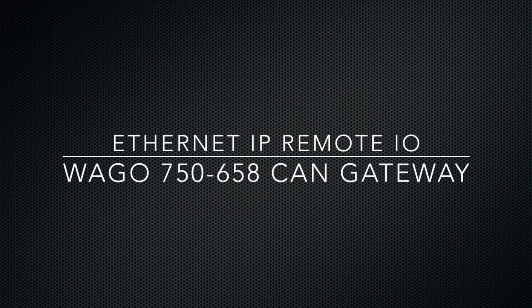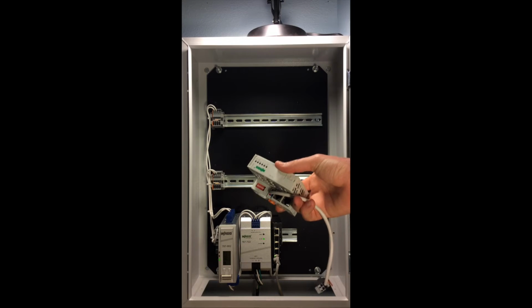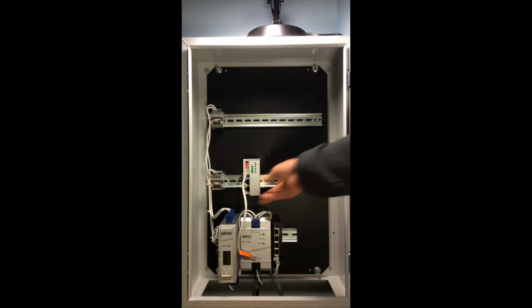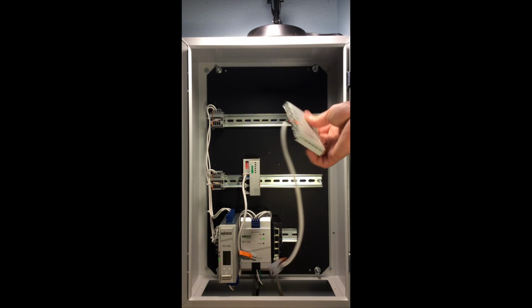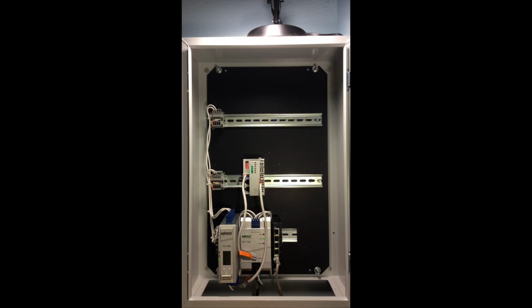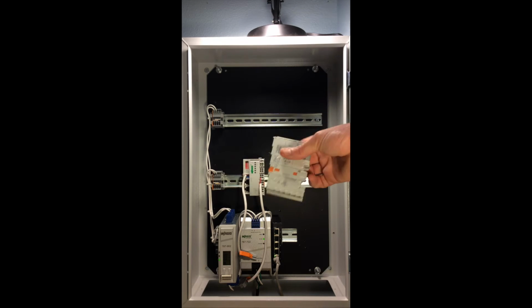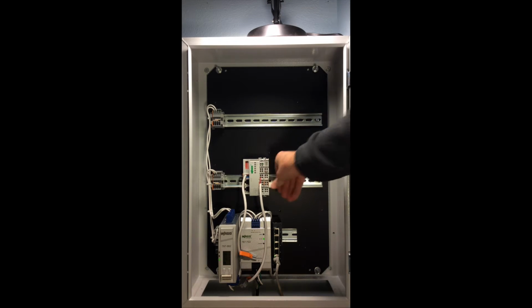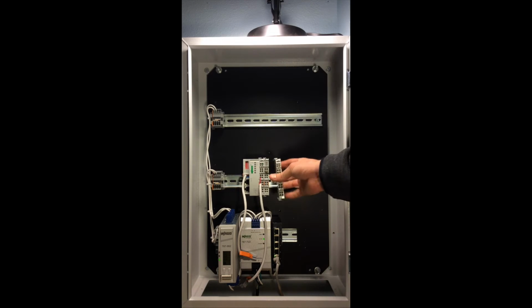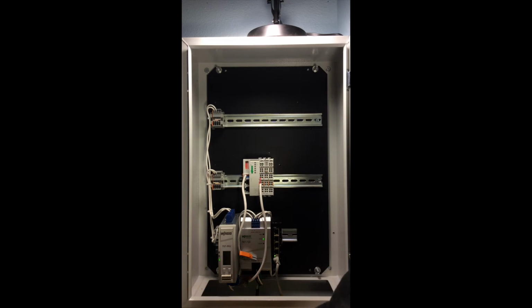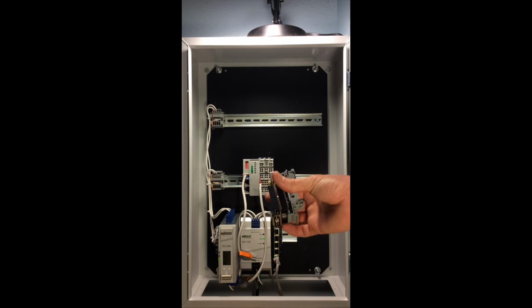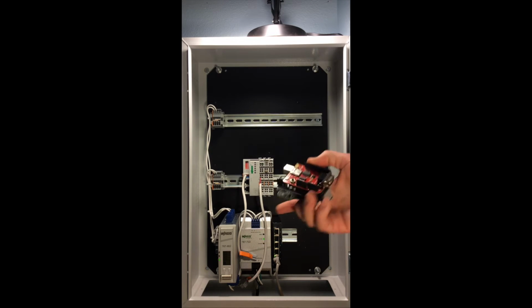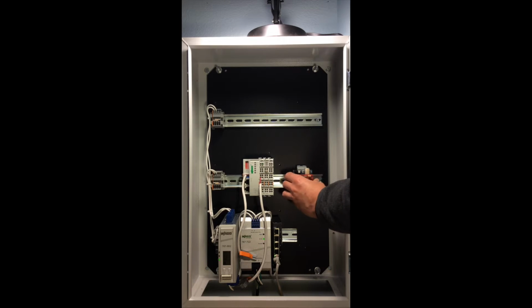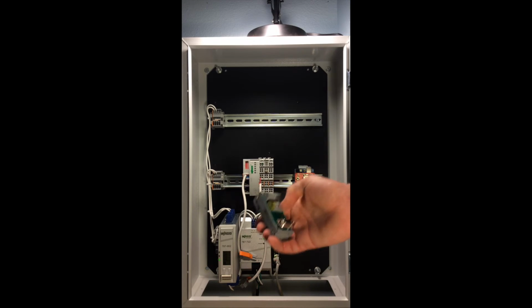This video will demonstrate adding CAN communications to Ethernet IP networks via WAGO's 750-658 module. We'll start with a 750-352 Ethernet coupler. We'll add a 750-602 24 volts DC distribution module, our 750-658 CAN gateway slice, and we'll close it with a 750-600N module. For our CAN simulator, we'll be using an Arduino Uno with a CAN daughter board mounted on top. And to connect all of these, we'll be using WAGO's D-Sub9 breakout board.